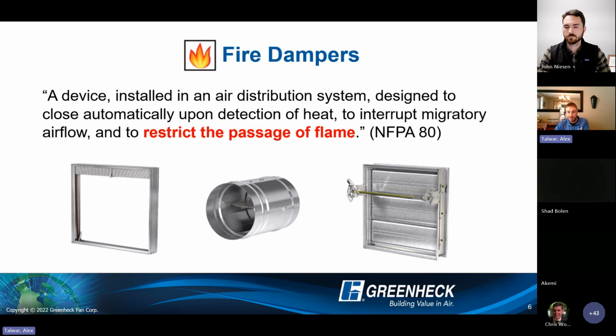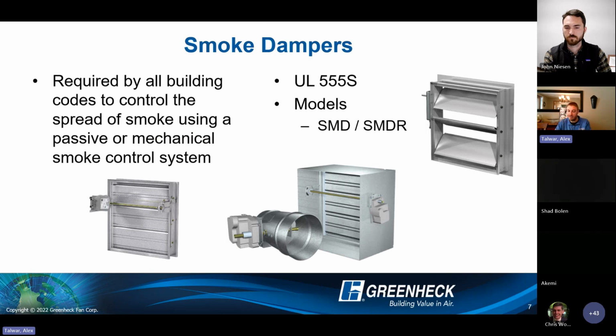Essentially, the purpose of these products is to restrict the passage of flame, as defined in NFPA 80. Ultimately they detect an increase in heat and close, and restrict the passage of flame from one area to the other, compartmentalizing these buildings into separate zones and preventing the spread.